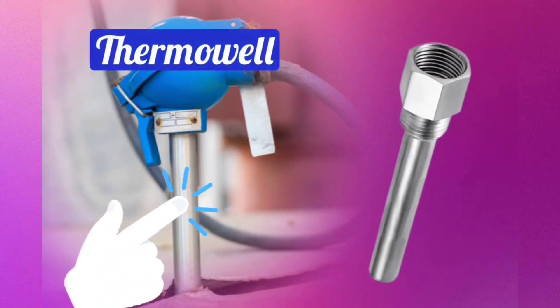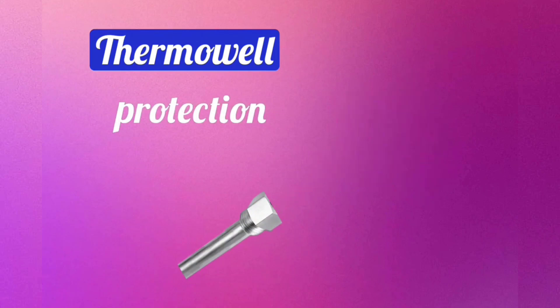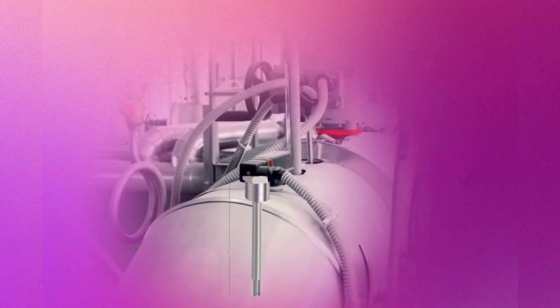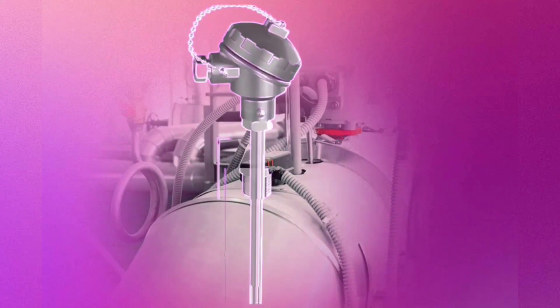Before installing RTD, a thermo well is also installed. Thermo well provides protection to RTD, and we can check it anytime by easily removing it from thermo well. First, thermo well is installed. Then, by using slide wrench, RTD is tightened in thermo well.